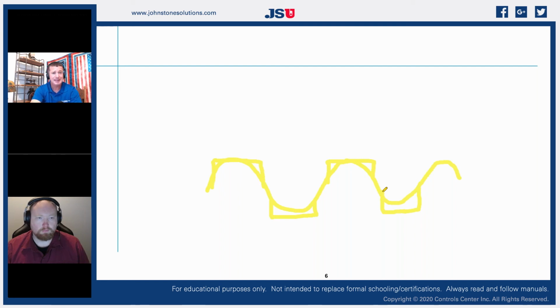When we say 230 volts, that's an RMS voltage. We actually have higher voltages than that. So what we're going to do here is we're just going to limit. We're going to cap it with our diodes. And then in the middle, we're actually going to add a grounded reference point, okay? It's pretty simple. So now what ends up happening is we have everything above ground is now going to be a positive signal, and everything below ground is going to be a negative signal. And we are going to use that to talk with. So number 1 on our communication circuit is that positive signal with reference to ground, and number 2 is a negative signal in reference to ground. They total about 5 volts DC.